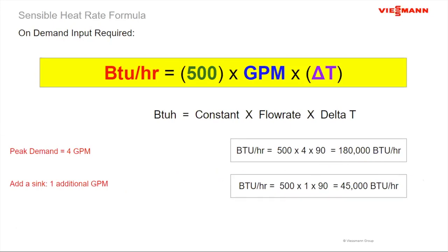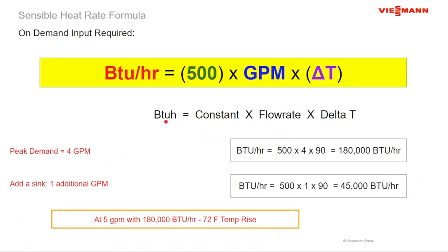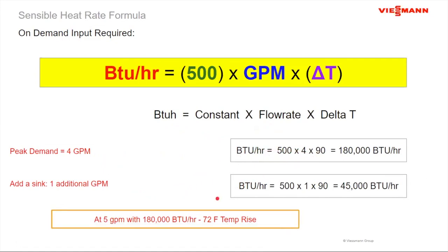The key when I do domestic hot water through a combi boiler, I get what I get and there's no way to stretch it out, okay? What will happen, and what you'll see with this, is if I have 180,000, I add in that extra gallon per minute. If I back my numbers out at 5 gallons per minute, because we can work this in both directions, if I have 5 gallons per minute and 180,000 BTUs, that means that when the two showers are operating and the single sink, I'm not seeing a 90 degree temperature rise. I'm only seeing a 72 degree temperature rise. And all of a sudden, the two people taking the showers in the two bathrooms, temperature's nice and warm, somebody opens up the sink, they feel the temperature drop at the shower. They go from a hot shower down to a lukewarm shower. So when we start to do combi boilers, it's imperative that I know and everybody agrees on the exact gallons per minute.